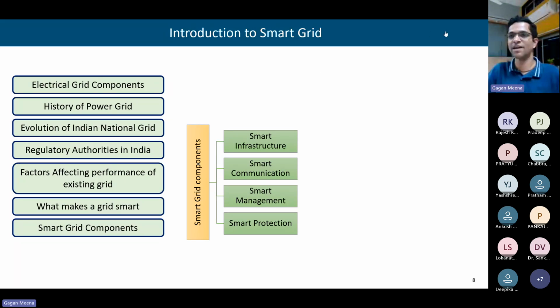We have to adaptively change it depending upon the system configuration. Topology also changes everything because bidirectional current is there, topology changes, current flow also changes. And the mode of operation of the inverter also governs whether the system is connected to the grid or islanded. That also determines the fault current. So there are so many parameters now which determine the fault current.